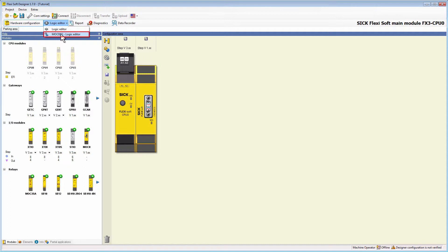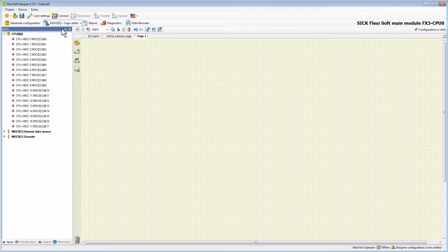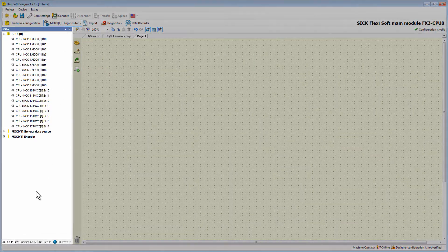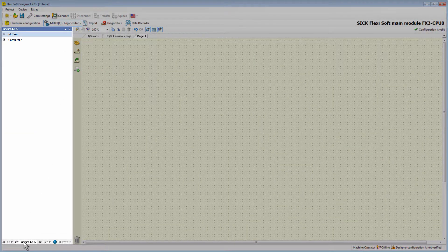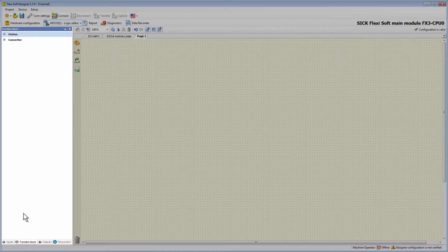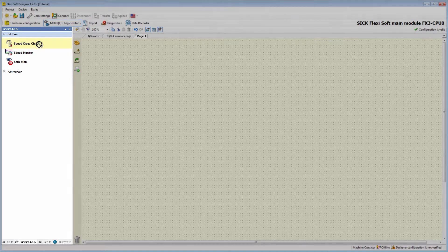You get there by using the drop-down menu of the logic editor. The field MOC0 logic editor only appears here if a drive monitor was selected in the hardware configuration. For every additional drive monitor there will be a separate MOC logic editor. The drop-down menu allows you to switch between the MOC logic and the CPU logic at any time, making it quite easy to route signals from the MOC to the CPU and vice versa. In the tab Function Blocks there are motion function blocks and converter function blocks. I am going to begin with the SpeedCrossCheck and drag it into the main window.